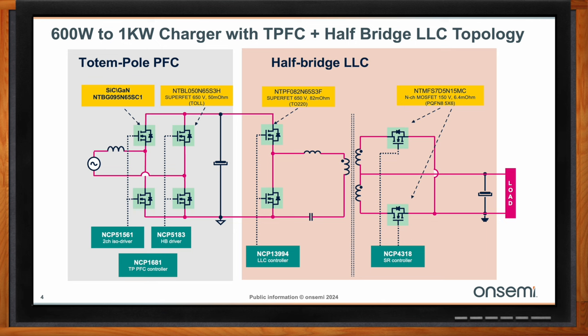Then as a second stage, we have implemented the hybrid LLC. So the input to the hybrid LLC is 400 volts DC or 450 volts DC. Then the secondary side is the battery voltage. Based on the battery voltage, it can be 20 volts, 24 volts, 48 volts, 60 volts or 80 volts. You can design your transformer accordingly.